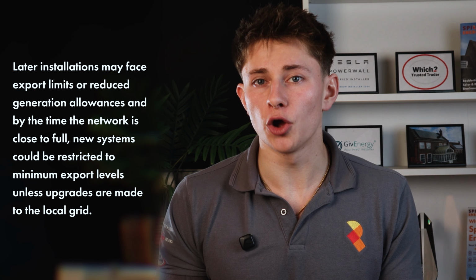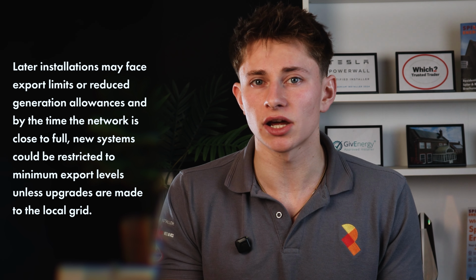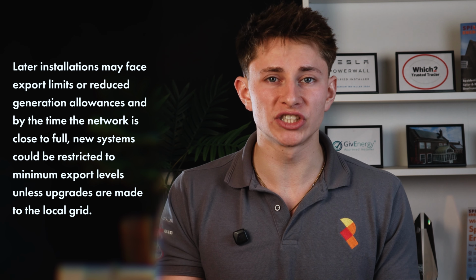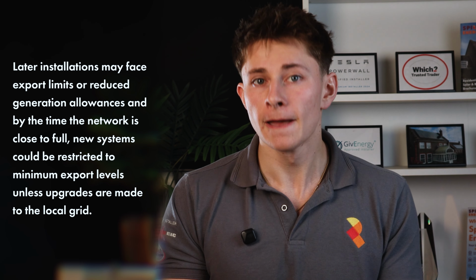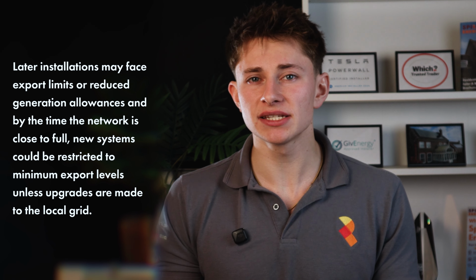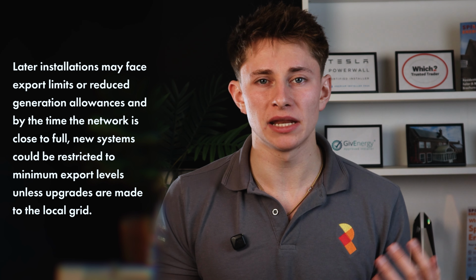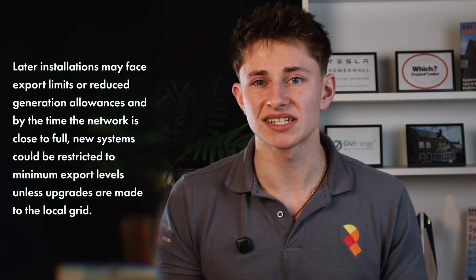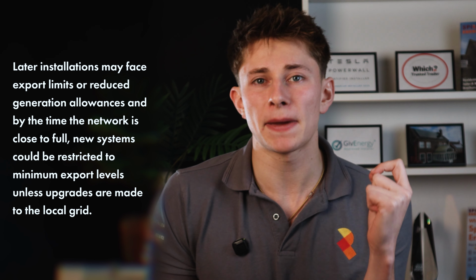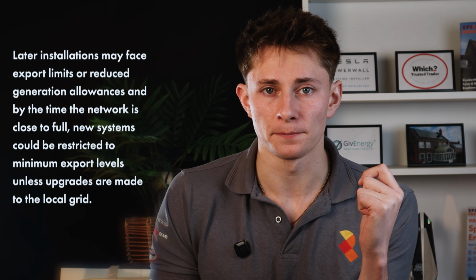So the later homes may be given restrictions such as an export limit or reduced allowed generation. By the time you get to the last few houses, they might only be allowed to install the minimum export allowance of 3.68 kilowatts, unless they pay for local network upgrades.